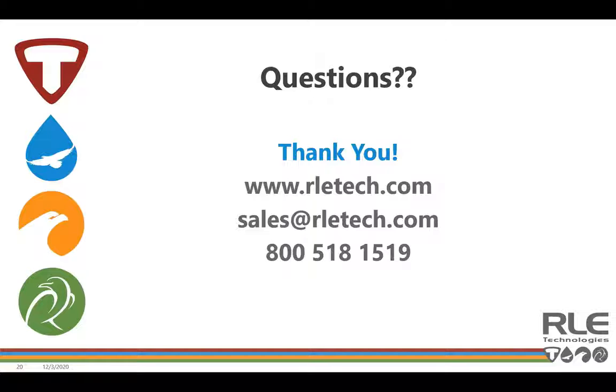Excellent question, and that was a great idea to put that matrix out there. The F200 actually serves as a leak detection device as well as a facilities monitoring device, so there's a bit of crossover there. It's considered a one-zone controller, so you can have up to 200 feet of our sensing cable or up to 4 spot detectors. It communicates via Modbus or SNMP. Think of an F200 in a network closet, maybe a small MDF or IDF room, a smaller scale application. In addition to leak detection, you can also tie in additional monitoring—there may be IP cameras in the space, or you may want to monitor environmental conditions such as temp only or temp and humidity. It also accepts 8 digital dry contact inputs and has 1 relay output function, which is nice when you're remote and need to turn something on or off. So the nice thing about the F200 is that it will cross over.